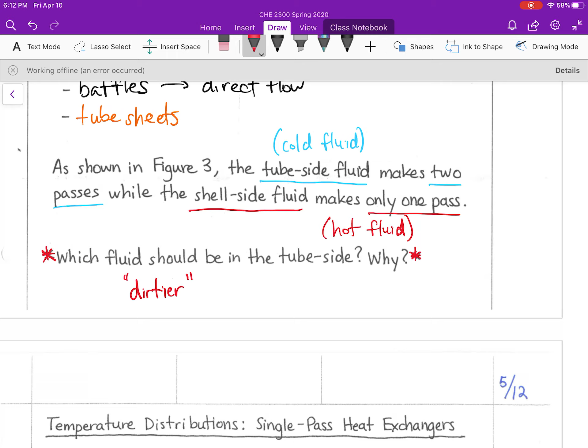So if my water is dirty compared to whatever fluid I am trying to cool, I would flow that through the tube side of my heat exchanger. As a general rule of thumb, I just look at my two fluids and ask which one is the dirtier fluid, which one will require more worry about fouling. If fluid A is the dirtier one, that's the one I'm sending through the tube side of my shell and tube heat exchanger in general.